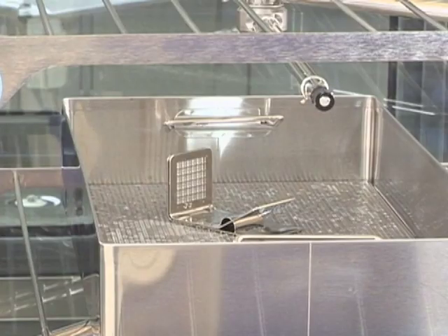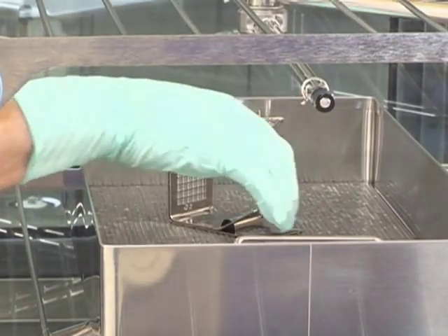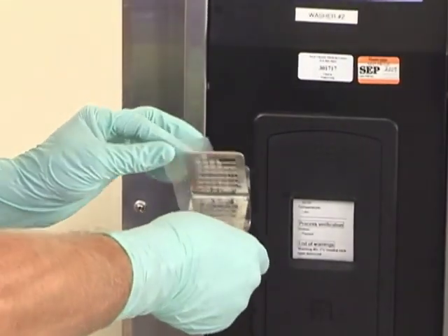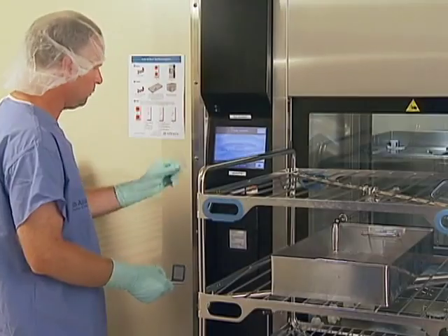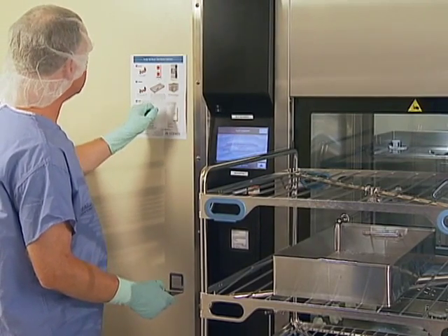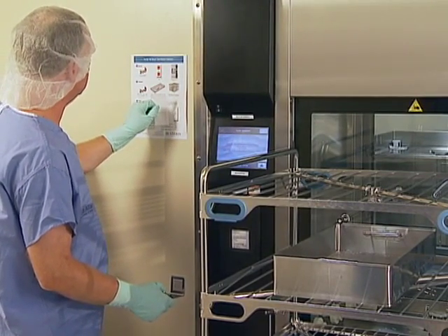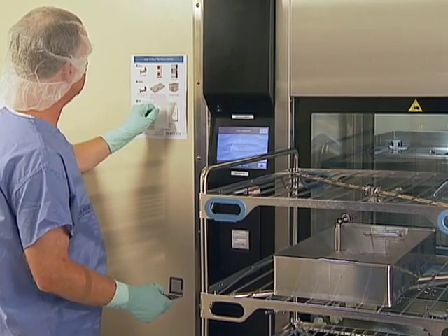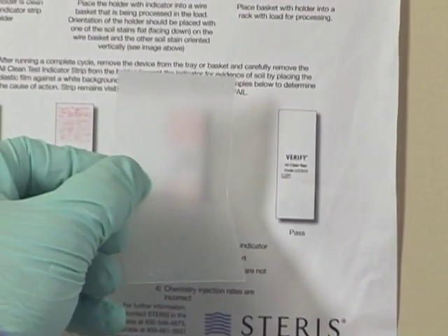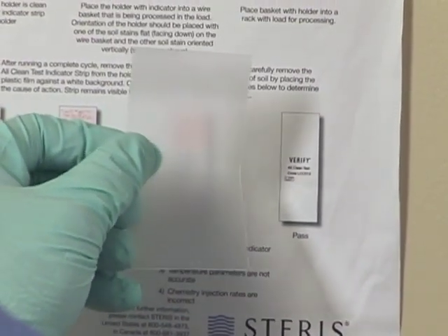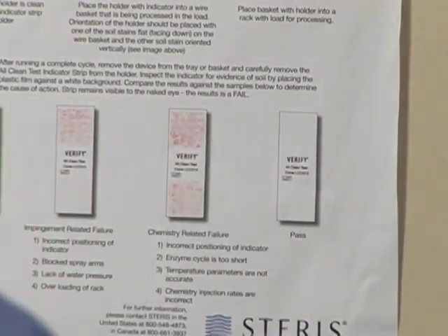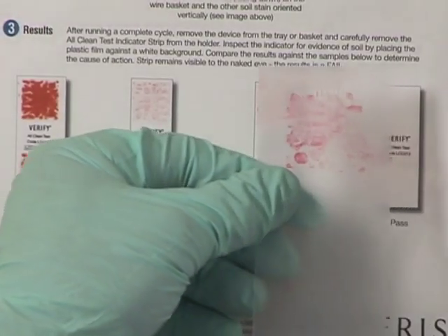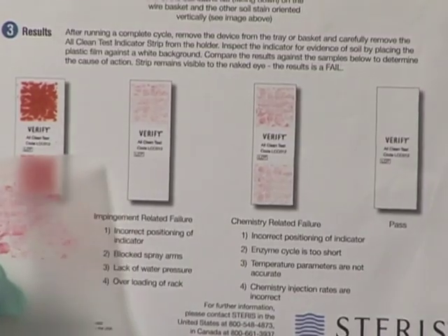Run a regular instrument cycle on the Vision single-chamber washer. After running a complete cycle, remove the holder from the tray or basket. Then carefully remove the All Clean Test indicator strip from the holder. Place the plastic film against the white background of the All Clean wall chart and inspect the indicator for evidence of soil. Compare the results against the samples of the All Clean wall chart to determine the course of action. If the soil remains visible to the naked eye, the result is a fail.